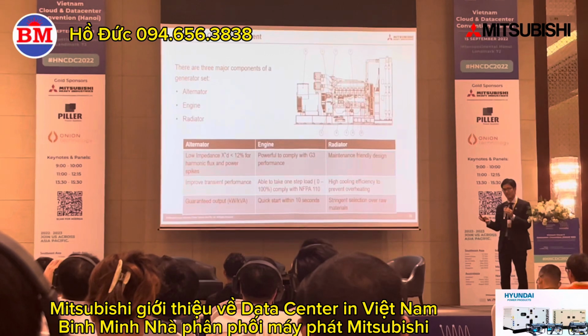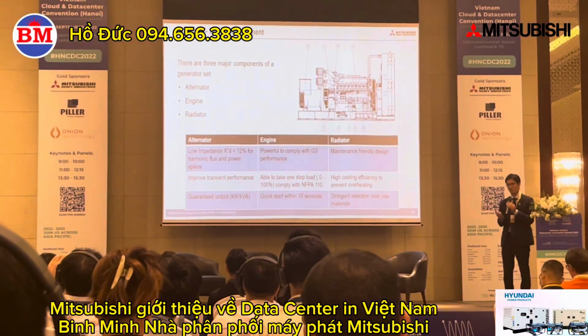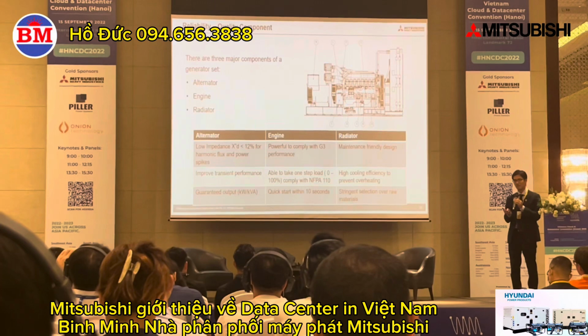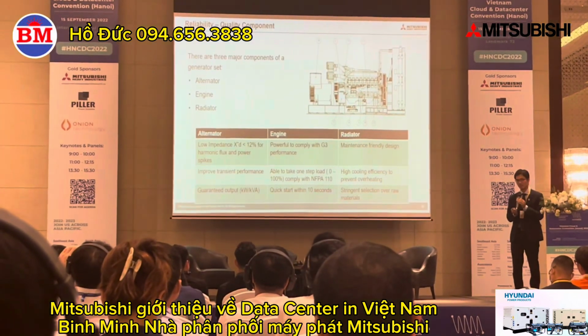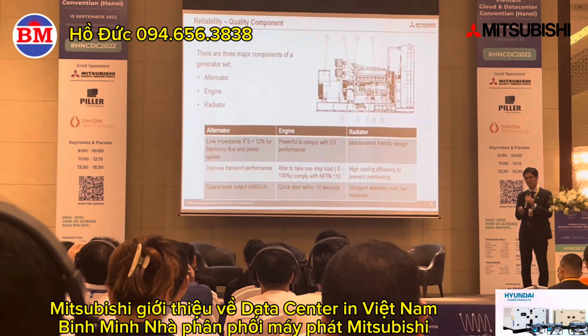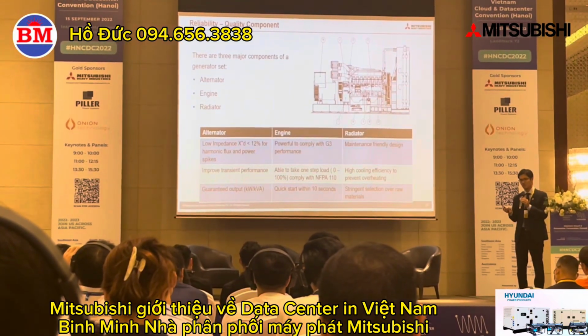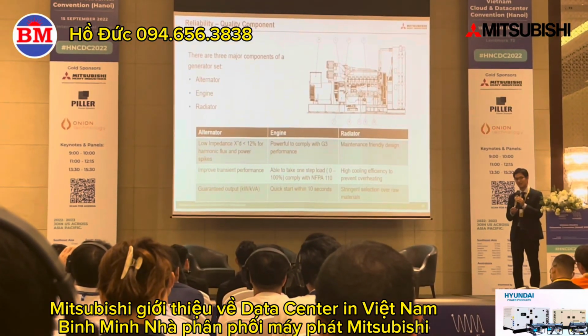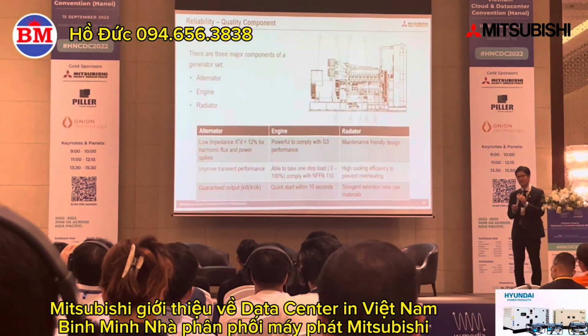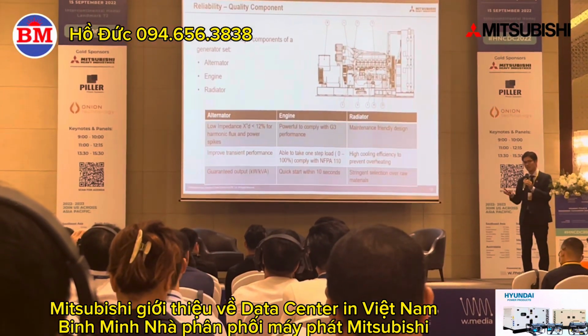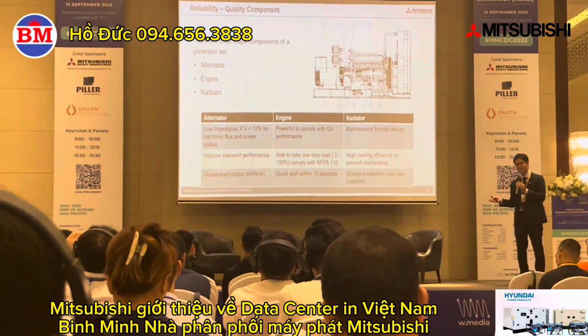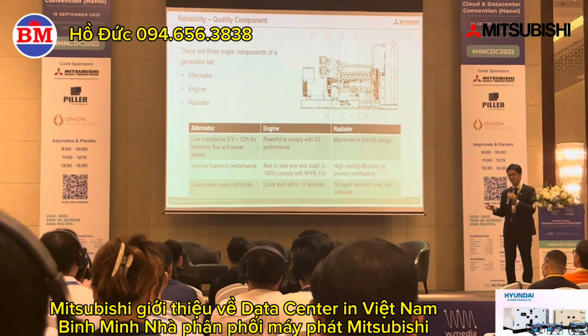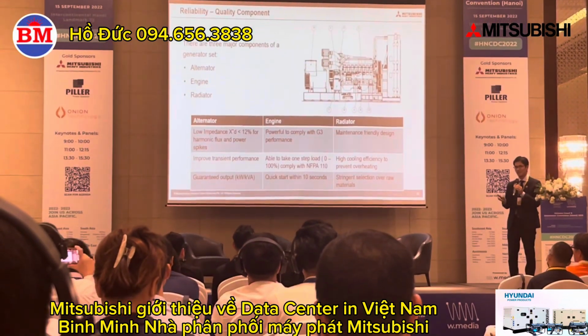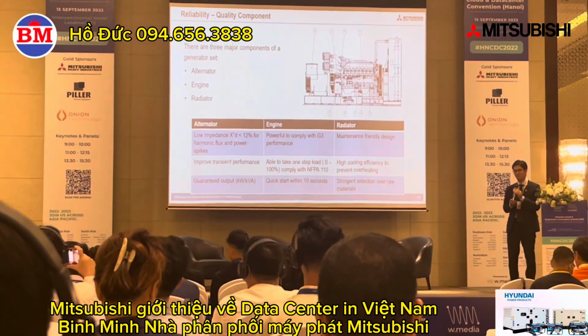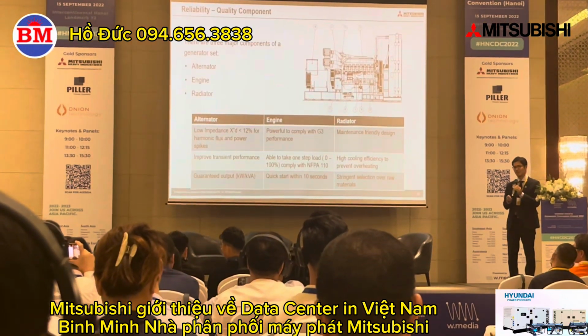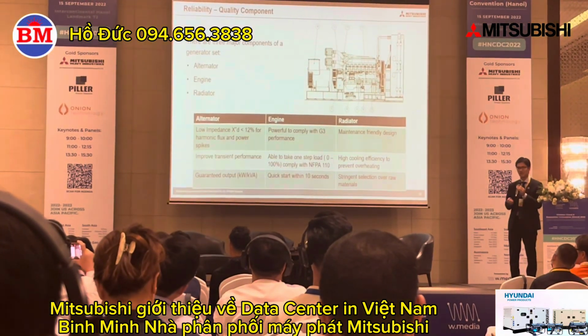This generator set has been used in data centers for more than 15 years. Over these 15 years, there is deterioration, so we assume deterioration will occur and build in some margin at the beginning, so that the diesel generator set can still run at 100% in the worst case after 15 years. This kind of design setting is very important, and when we explained this to customers, they were very happy to know the generator set can run continuously for 15 years.